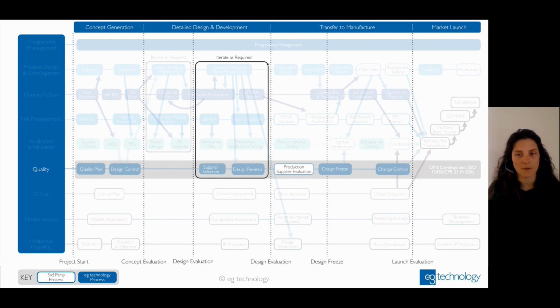You need to be ISO 13485 certified. Some smaller startups prefer to subcontract that out to an organization that acts as legal manufacturer and has ISO 13485 certification, so you can look into doing that as well. But either way, within your development program, you need to think about your strategy and how you're going to set that up and have it in place for launch.